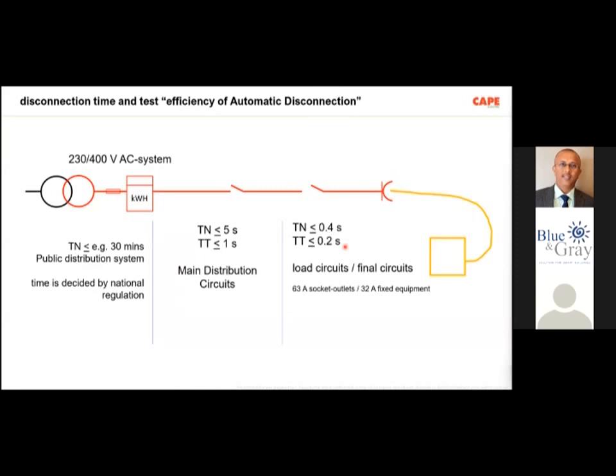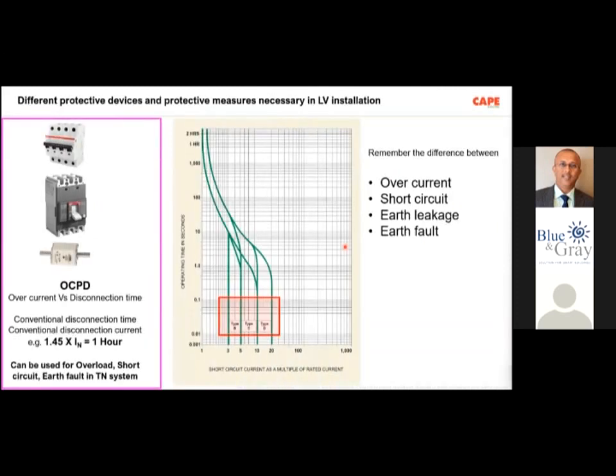So what I wanted to explain to you is, before making the test, you must understand what kind of safety measures are implemented there. What kind of system earthing is it? Is it a TT system or a TN system? And if it is a TN system, what kind of distribution is it? Is it the final distribution or the main distribution circuits? Based on that, first we need to find out the maximum disconnection time. Then based on the maximum disconnection time, you have to select the appropriate protective devices such as OCPD.